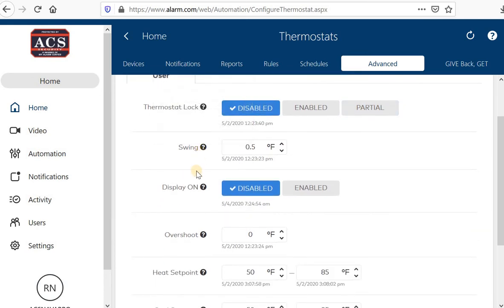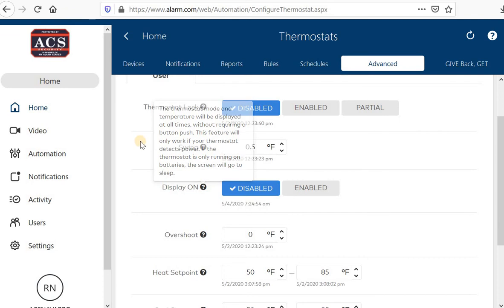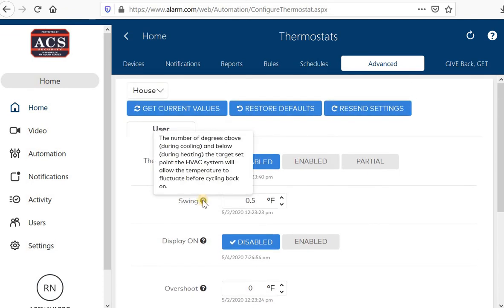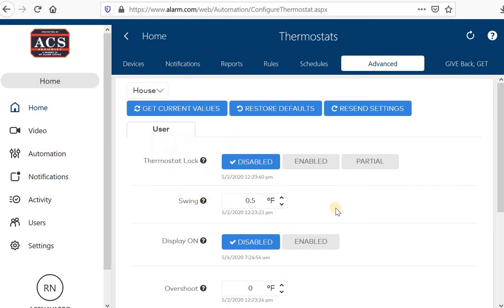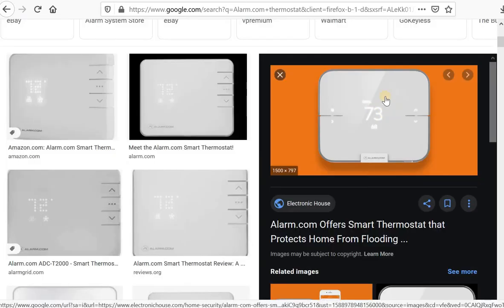Swing. By the way, these little question marks will allow you to get information. For example, it says swing here. If you just hover over that, it says the number of degrees above during cooling or below during heating the target set point. The system will allow the temperature to fluctuate before cycling back on. This is 0.5 degrees. For example, if I have my thermostat set at 70 degrees in air conditioning mode, if it gets to 70.5, it will go ahead and kick on to maintain that temperature. It has my display on or off. You can have that digital display that you see here either on or off.